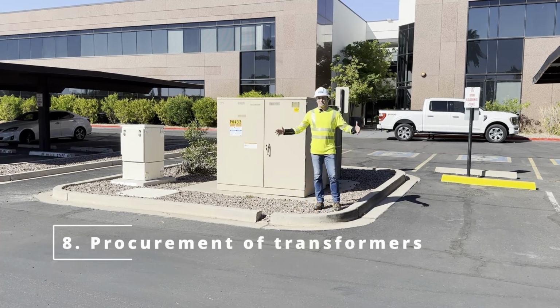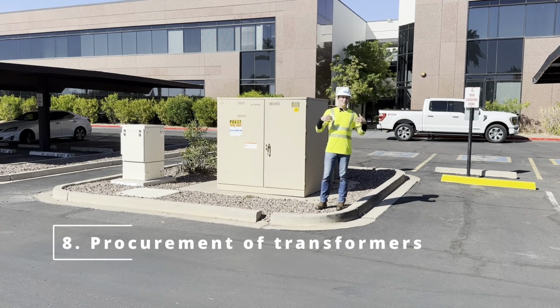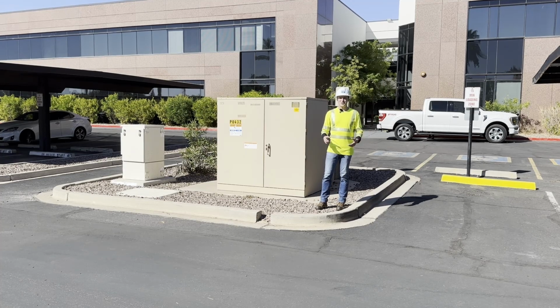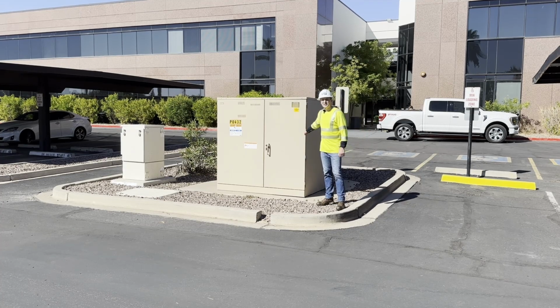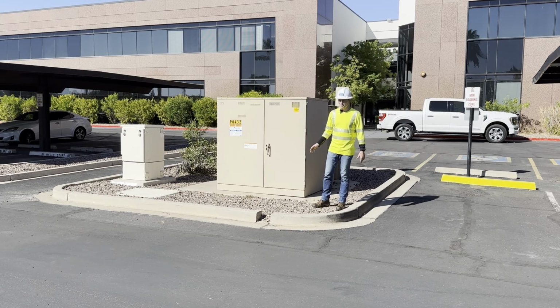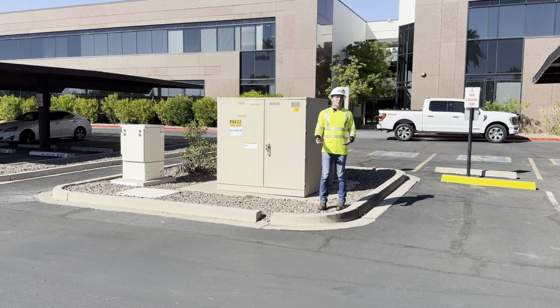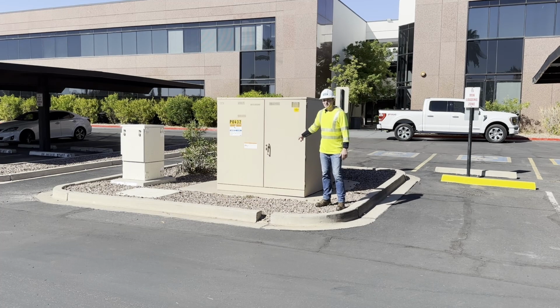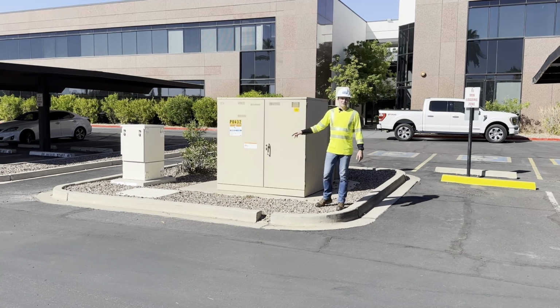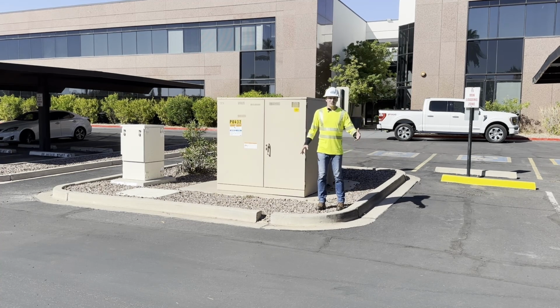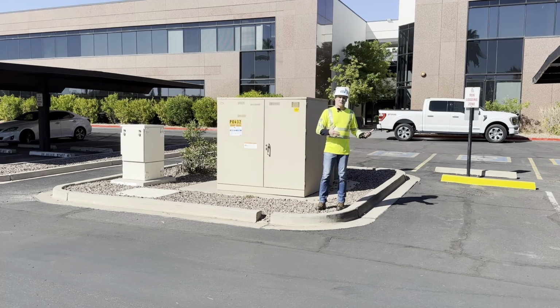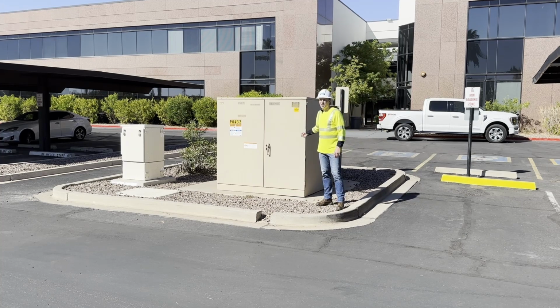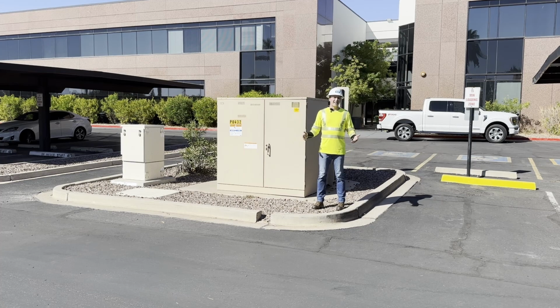Number 8, procurement of transformers. If you have developed EV charging projects in the past, you already know that getting the utility to buy these at the time you want them is one of the most challenging, frustrating parts of the process, because you as the developer and future customer don't own this - it's owned by the utility for secondary services. Primary metered services, where you're taking primary voltage from the utility, you'll actually own these, but for most projects today, you're taking secondary service from the utility.